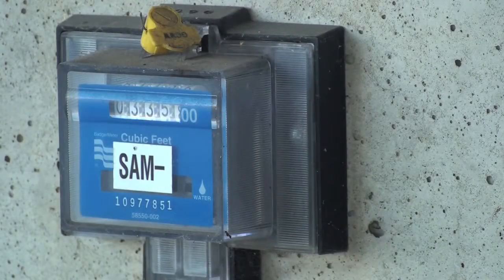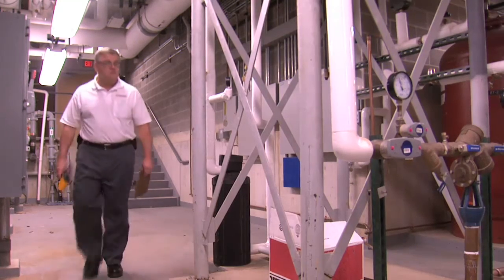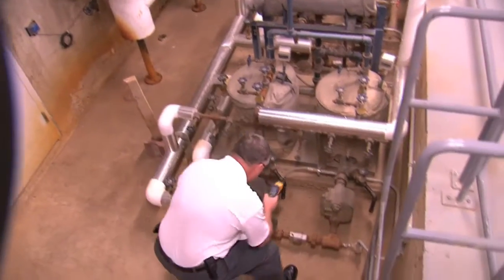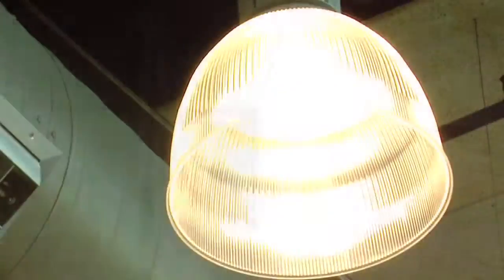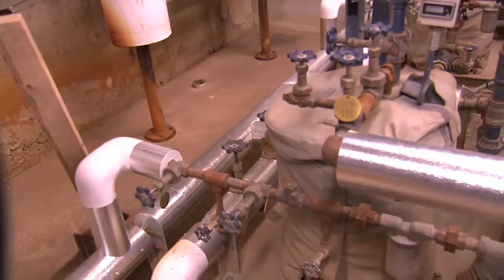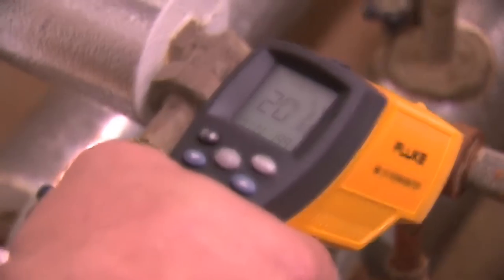The first step is metering our buildings. The second step is to do building energy audits. We go into a building into the mechanical areas — these are areas nobody goes into, sort of the belly of the building. We look at steam pipes; if it's uninsulated there's a lot of heat loss to the piping, so we replace that. We have steam traps through which steam is blowing through, so we replace that. Any kind of lighting that's inefficient we retrofit with T8s, which is more efficient. The third step is to implement the projects. We've implemented 35 projects, and the net present value of just these projects is about $3.8 million over the last few years.